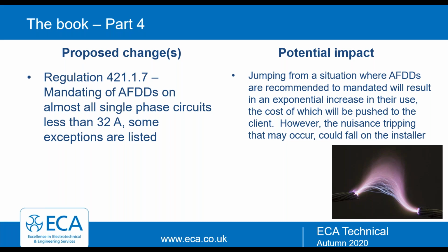Are they mandatory? No, currently it's only a recommendation. Okay. And this new proposal for 421? This would see AFDDs mandated, so a shall, on almost all single-phase circuits less than 32 amp. The limitation of 32 amps is more a manufacturer thing rather than anything more specific. So 32 amp or less, all circuits.